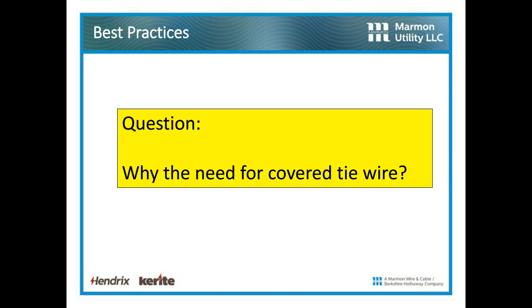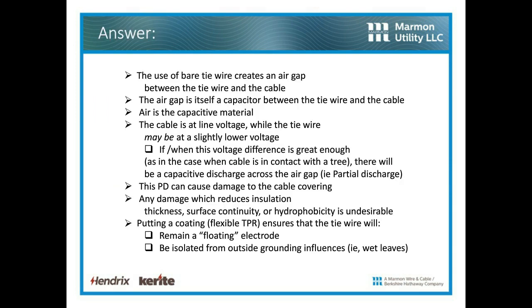Why do I need covered tie wire? Well, the use of bare wire creates an air gap between the tie wire and the cable. The air gap itself is a capacitor. Air is a capacitive material. The cable is at line voltage, while a tie wire may be at a slightly lower voltage. If and when this voltage difference is great enough, as in the case when the cable is in contact with a tree, there'll be a capacitive discharge across that air gap, also known as partial discharge.